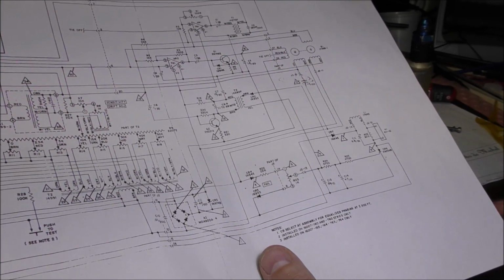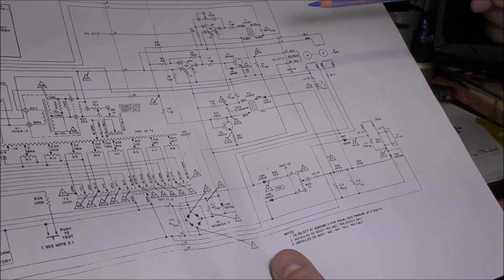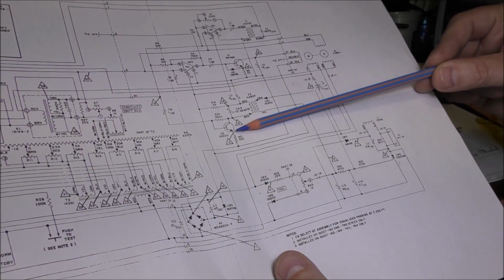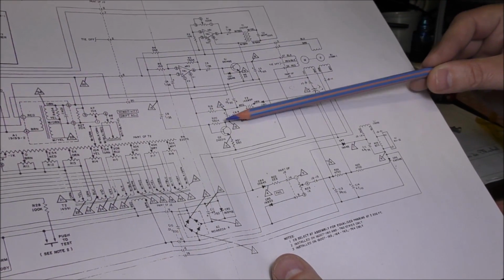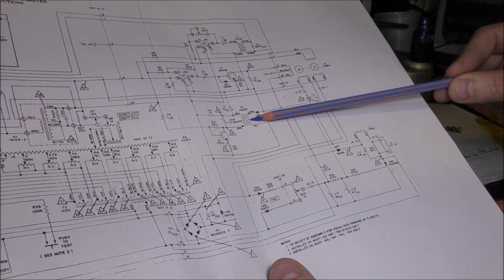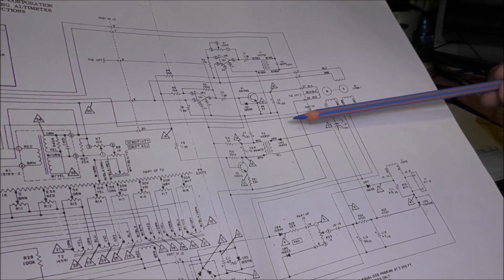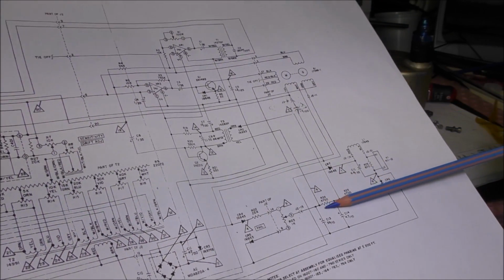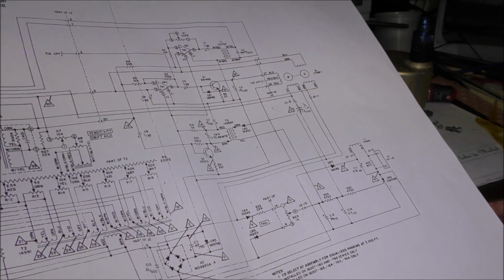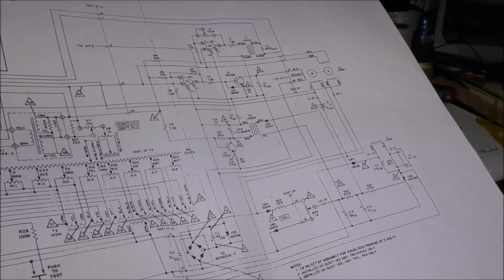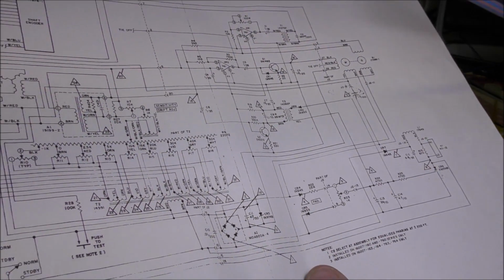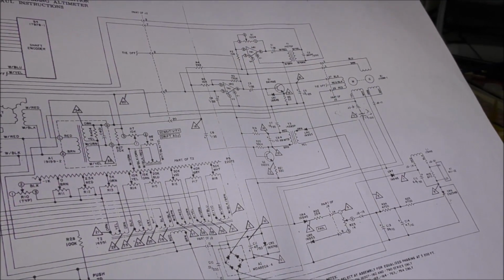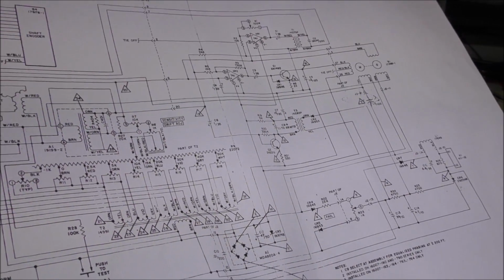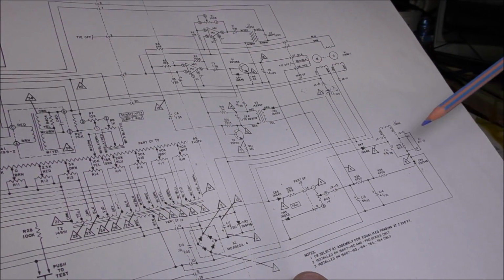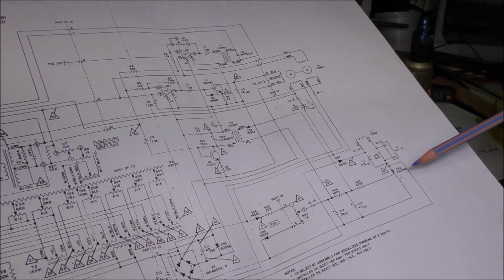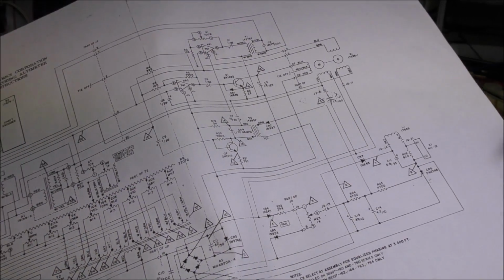And there is also a condition regarding the servo control loop. The input voltage of the amplifier is fed to this amplifier here. This is this line. So the voltage at the input here is amplified, and we have this transformer, and the output voltage of this transformer is rectified and placed in series with the gate of this SCR. And if the input voltage of the amplifier is too high, that is to say, if the loop is not closed, because when the loop is closed, we have always a voltage which should be close to 0, if there is any problem, this voltage can be above a given limit. And in this case, there will be a negative voltage at this point here, and this will prevent the conduction of the SCR, and in this case, the flag will not be activated.